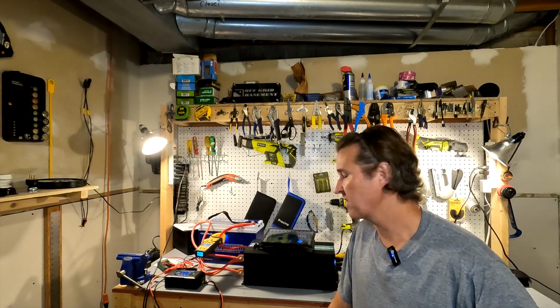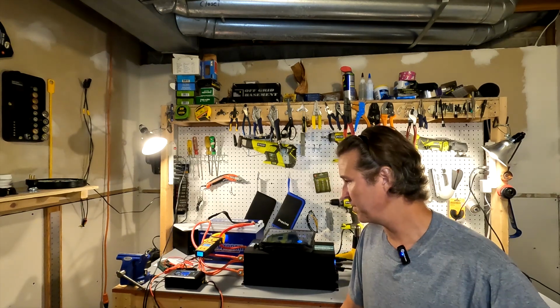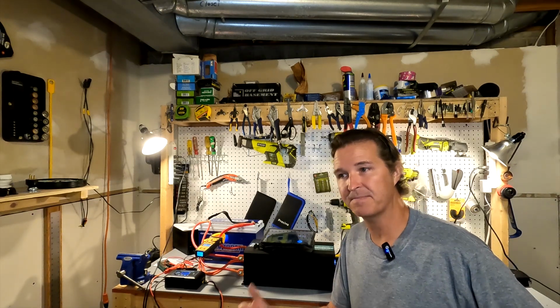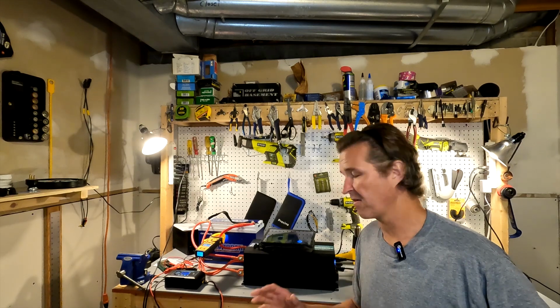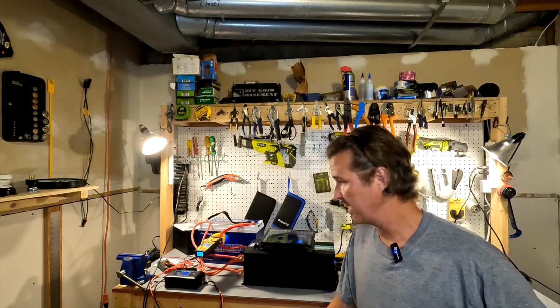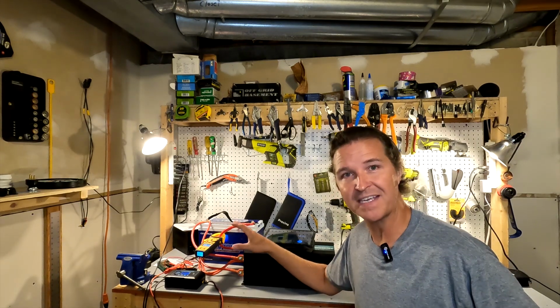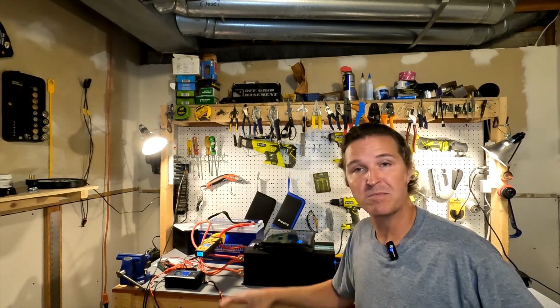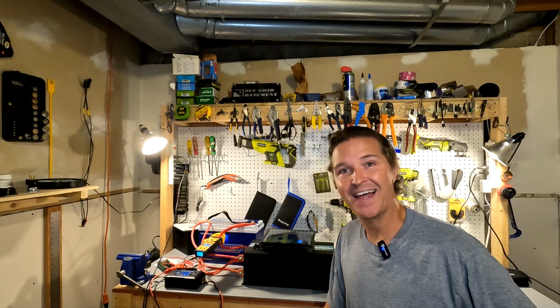So what did we learn from that test? Well, we learned that this battery could easily pull 130, 135 amps for 5 minutes, no problem. With the proper cable sizing and the proper inverter, the battery terminals did not really even get that hot. I don't think they even reached 110 degrees, which is completely fine for a battery.